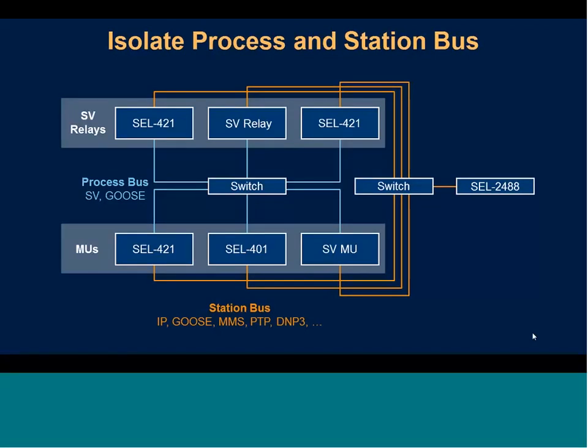The other network is generally what you would think of when you're thinking of Ethernet traffic in a substation today, and that's station bus. This is for anything that is non-protection critical. So you can still have GOOSE messages, just like you're using today, but you would also have all of your IP traffic, possibly MMS, DNP.